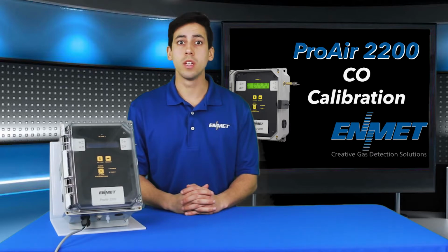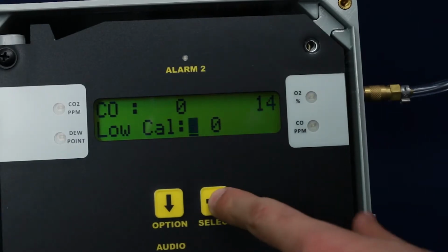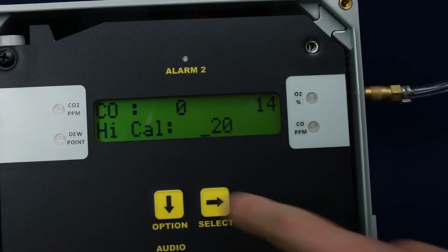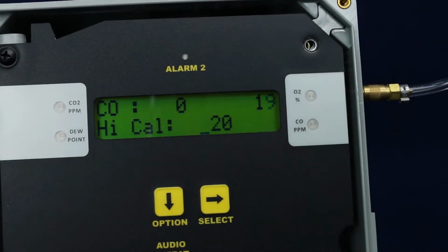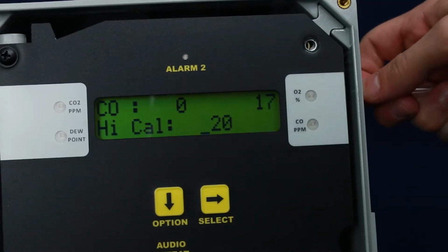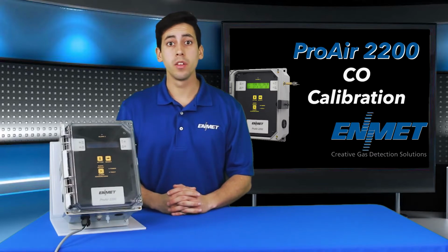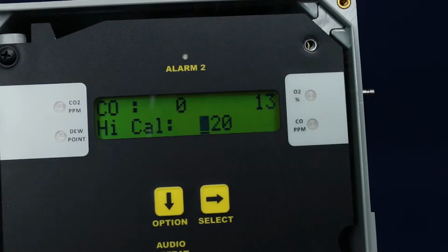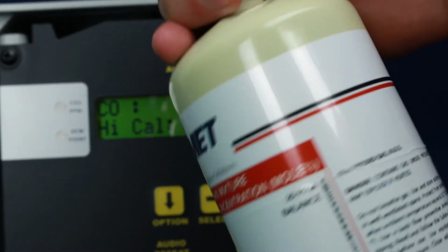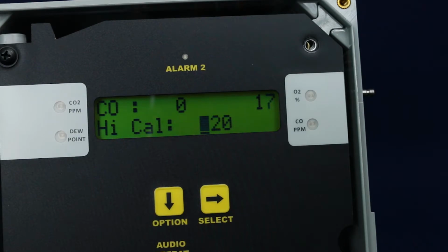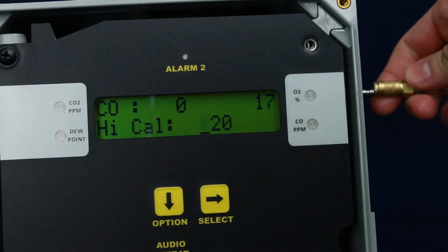At this point, the signal should be stable, so you will accept the calibration by pressing the Select button to move the cursor over to the right, and when it gets to the last digit, you will press Select one more time for it to accept the zero calibration. Now, for the HiCal, you will need to attach the 20 ppm carbon monoxide calibration gas cylinder to the regulator and connect the regulator to the instrument inlet and open the valve on the regulator.